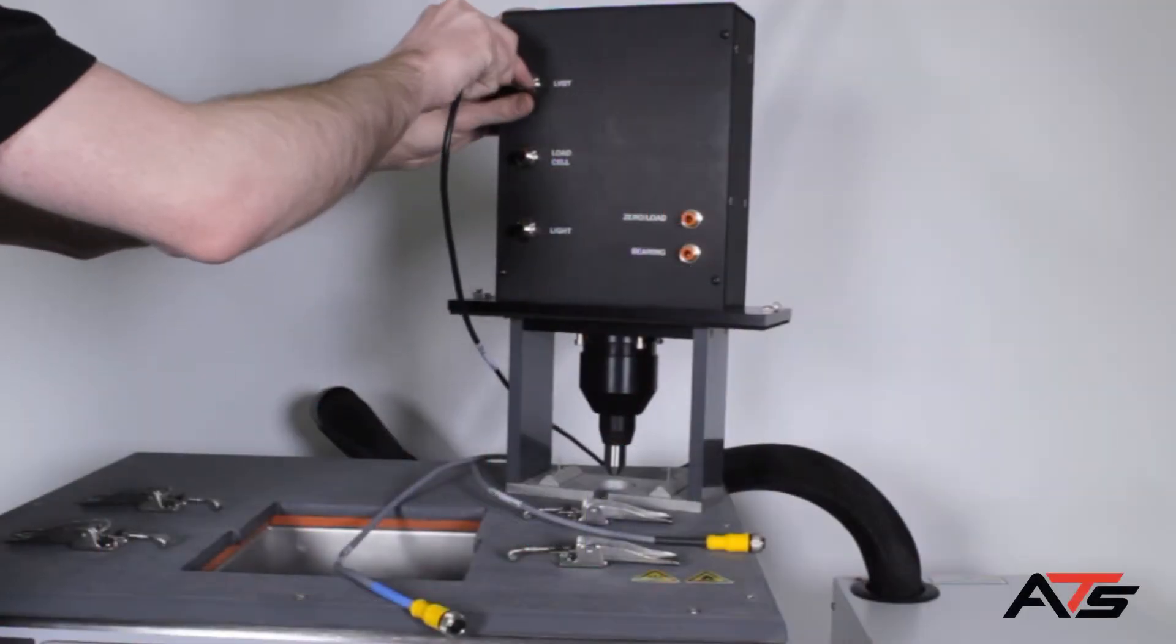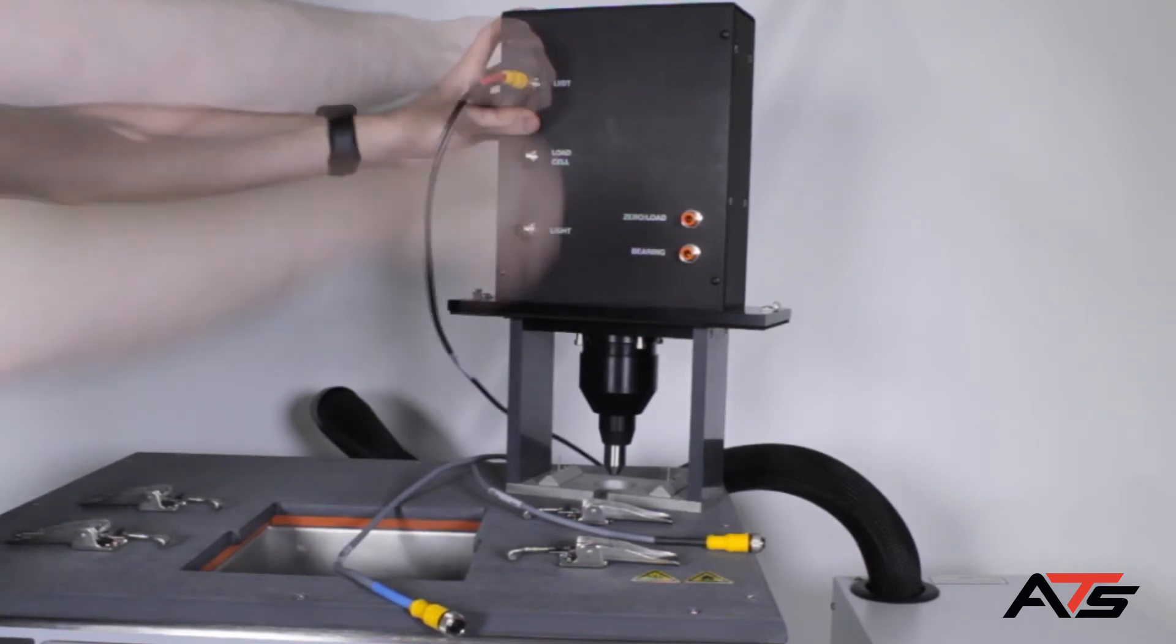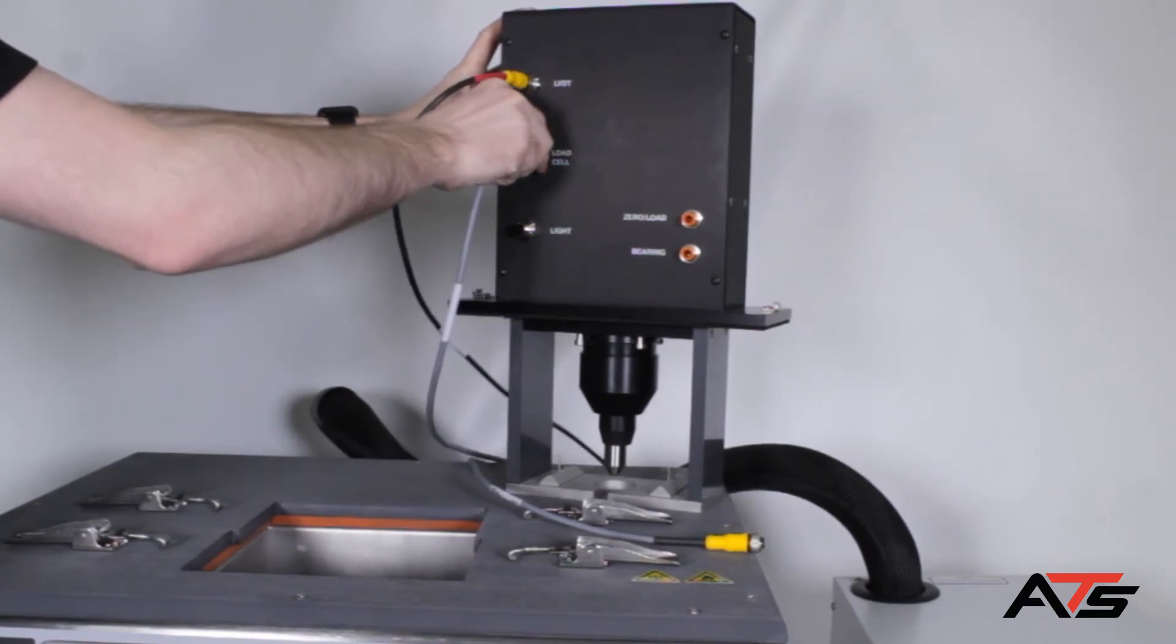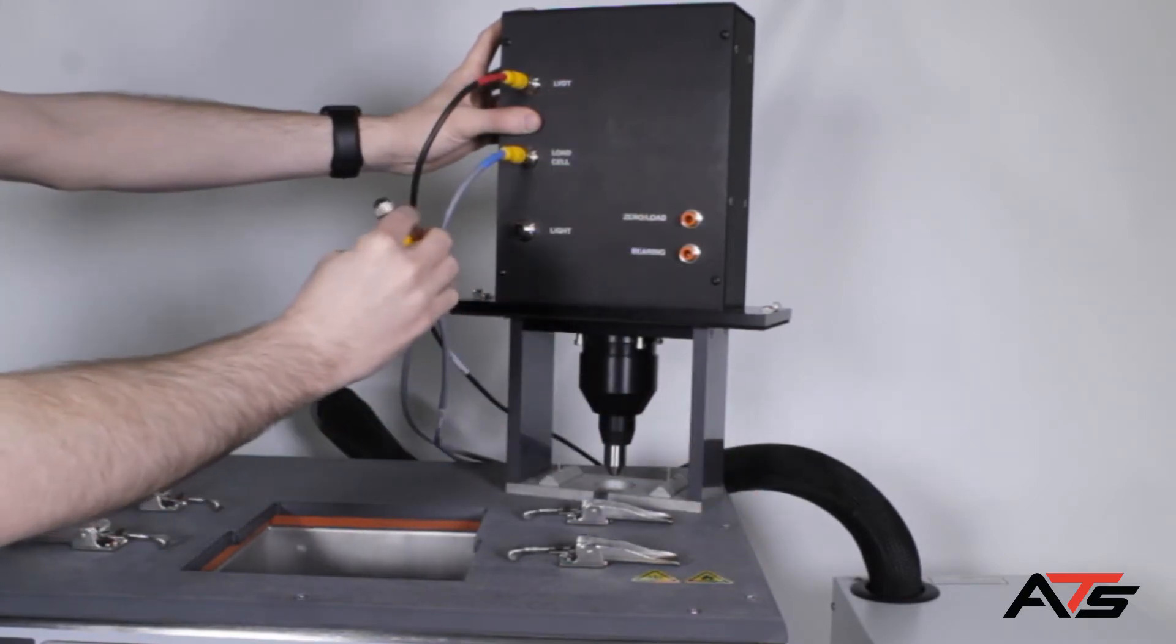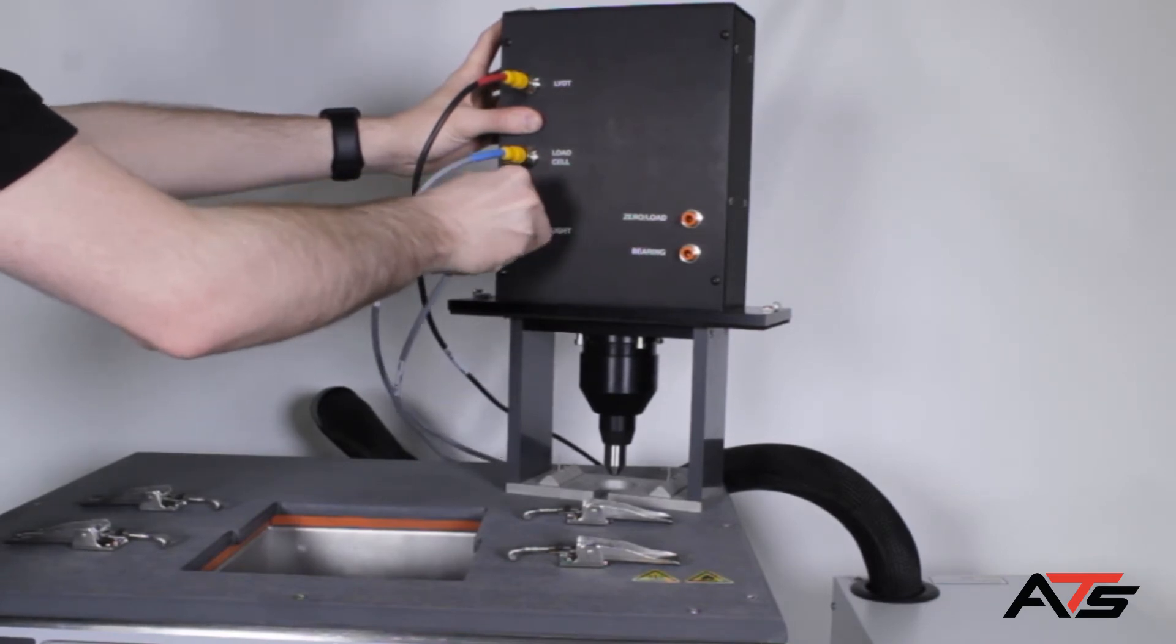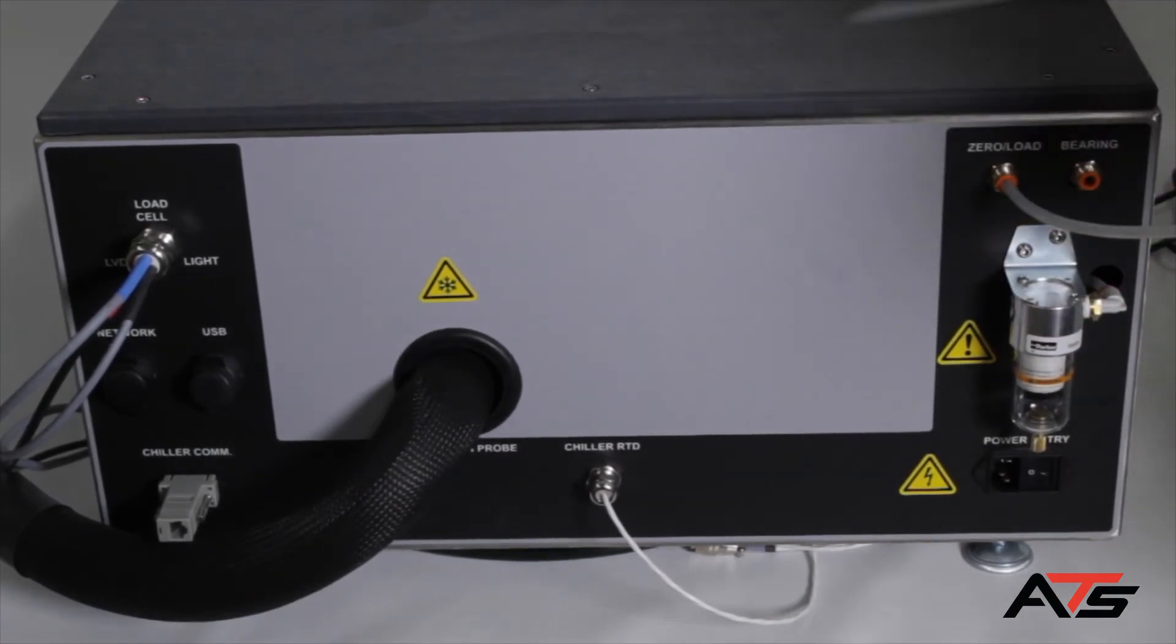Connect the electrical cables from the back of the base unit to the back of the load frame assembly. Connect the air hoses to the ports on the rear of the base unit and to the ports at the rear of the load frame assembly.